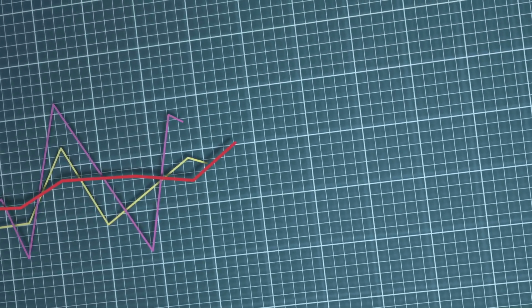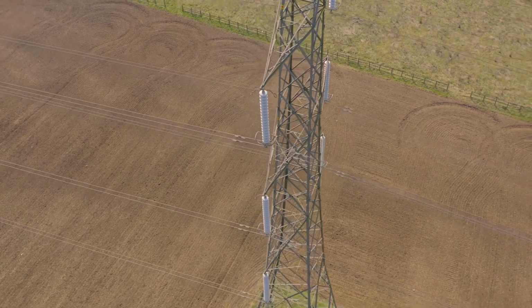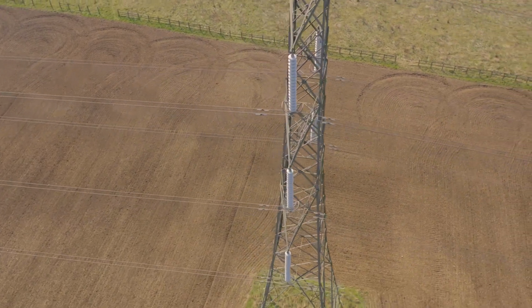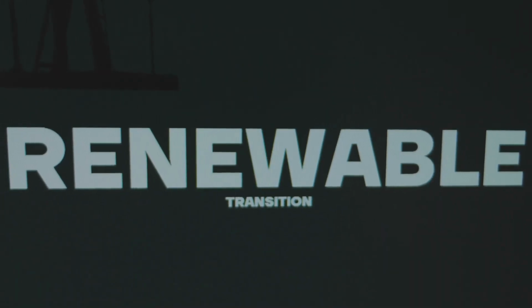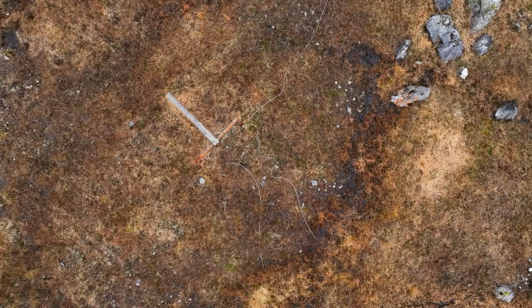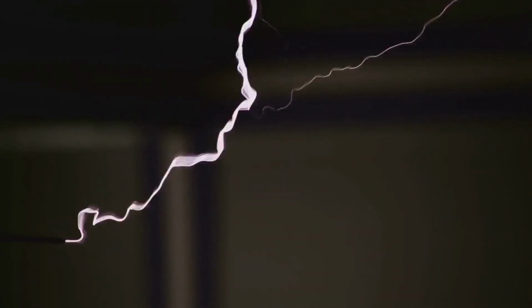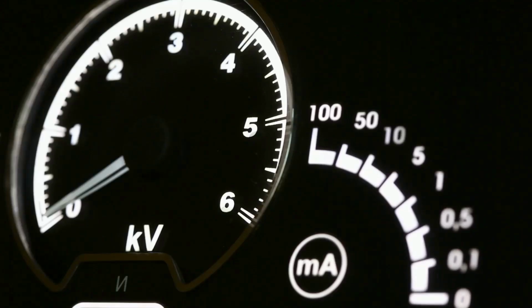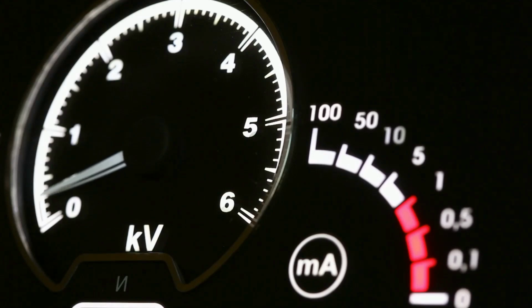The key regions include mandatory operation region, the DER must remain connected. Permissive operation region, the DER may stay connected. Trip region, the DER must disconnect if limits are exceeded. For example, a Category 2 DER must ride through a 50% voltage sag for at least 0.16 seconds, and it must withstand 88% voltage for up to 20 seconds.